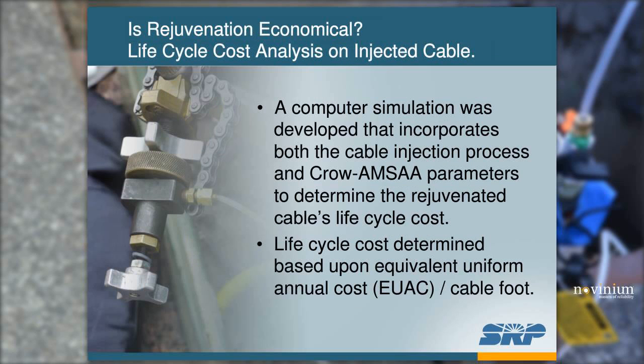Next thing we want to know is the economics. So to do this, again, we developed another computer simulation that is going to mimic this injection process. We're going to pull in our AMSAA model to put a fault component on there, and then we're going to determine life cycle costs for replacement versus injection based upon equivalent uniform annual cost per cable foot.